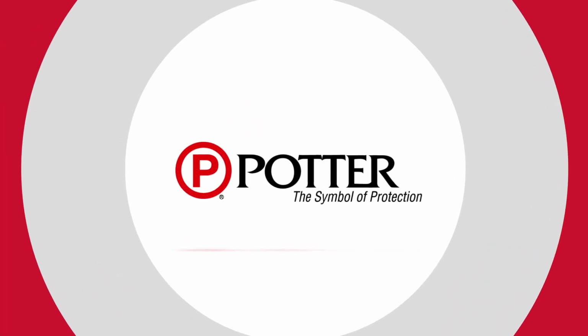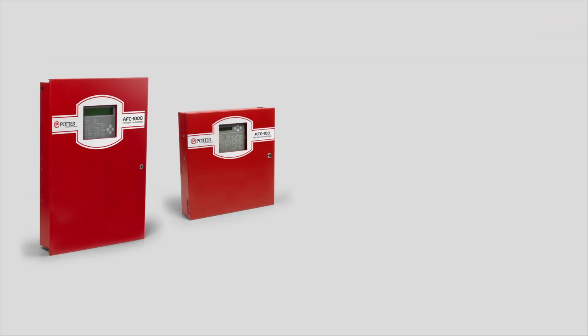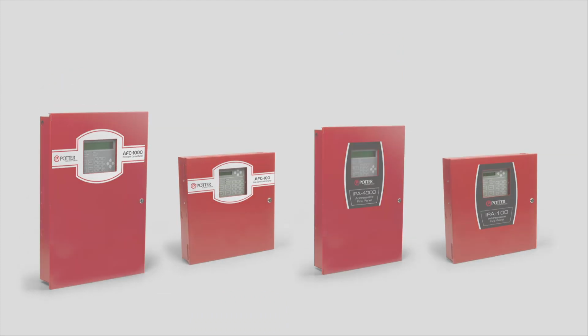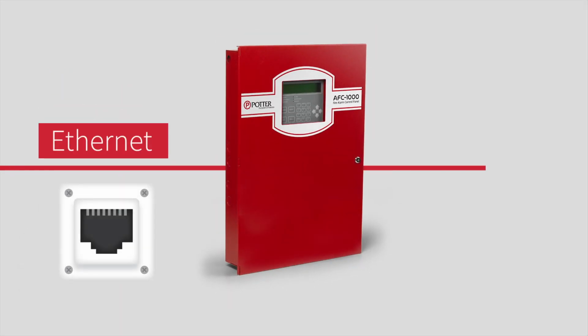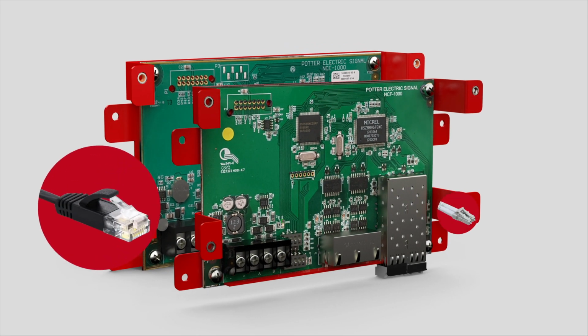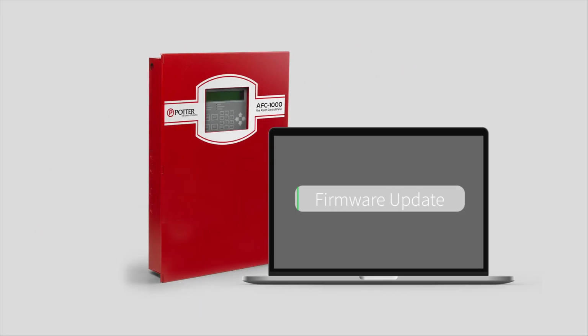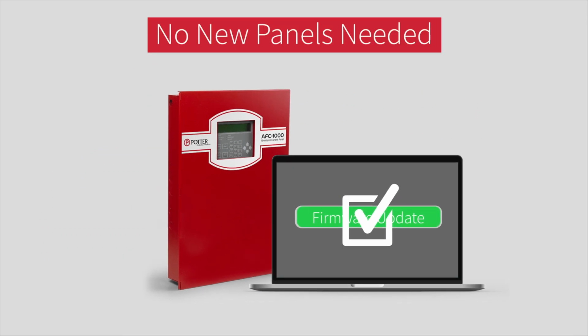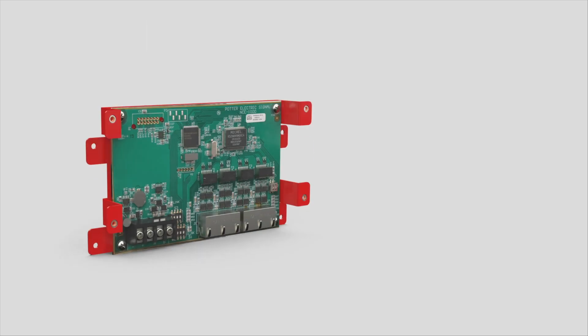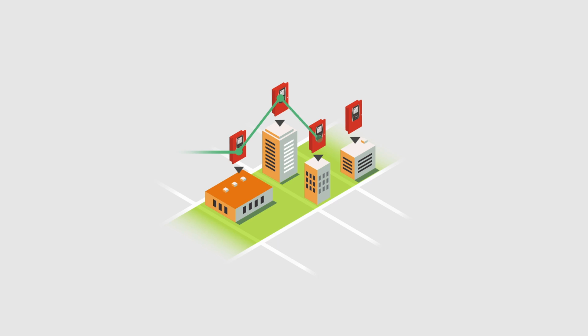Potter's peer-to-peer networking solution allows new and existing Potter addressable fire alarm panels to communicate on a dedicated Ethernet or fiber network. With the simple installation of an Ethernet or fiber-based P-Link card and a panel firmware update, users can network their existing systems without needing to purchase new fire panels. Ethernet and fiber cards are interoperable, and both types can be used within a network.